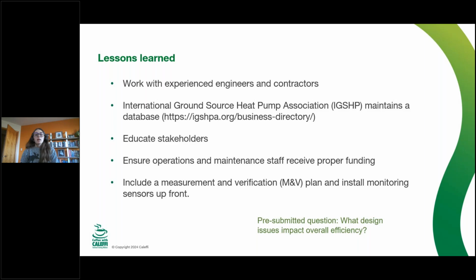And then include a measurement and verification plan and install monitoring sensors up front. In the military, you're required to do reporting on your energy systems, and we often see that this doesn't happen for ground source heat pumps because they don't have a measurement and verification plan during installation, and they're not installing the proper monitoring and sensors during system installation. This is really important to make sure your system is functioning properly and as expected throughout its life, and it's an easy way to identify issues and catch them before they become bigger problems.